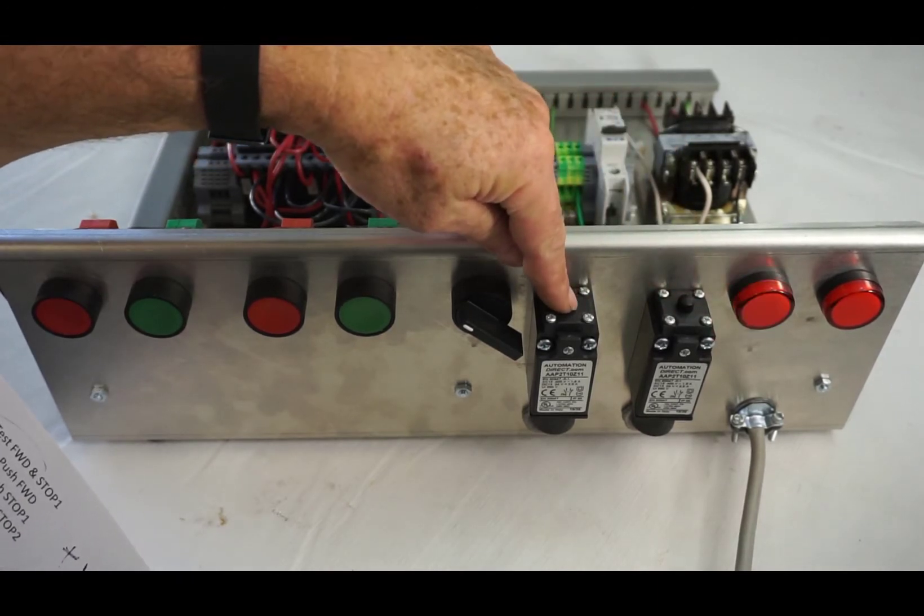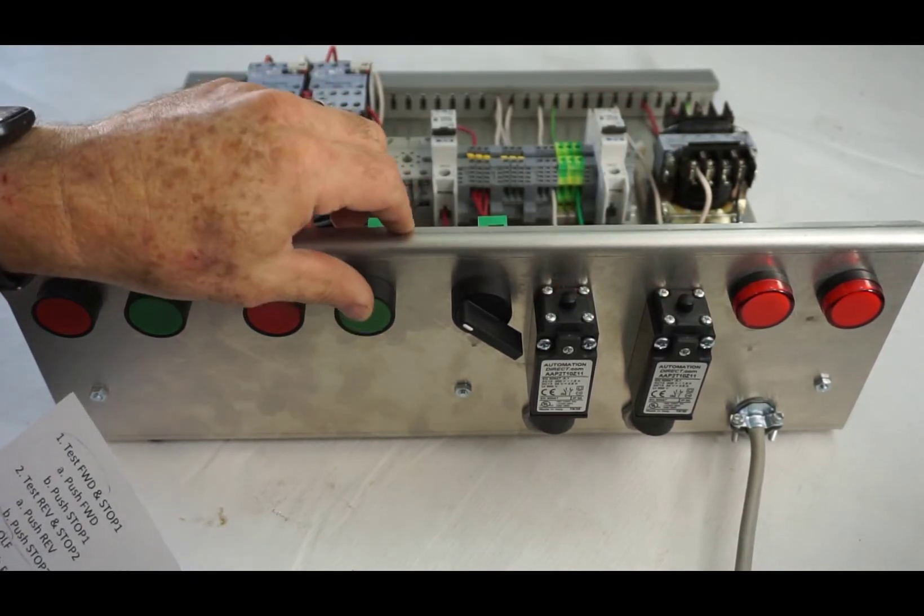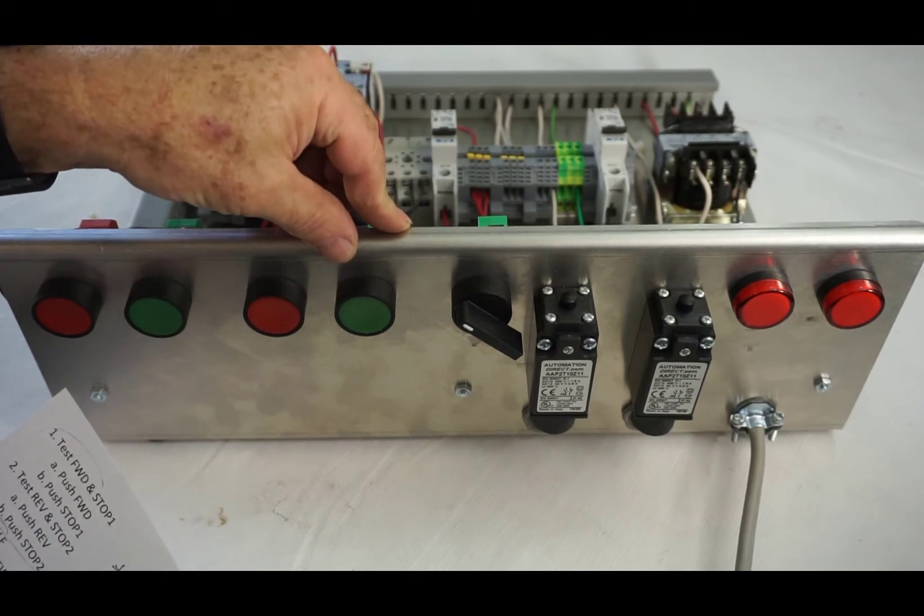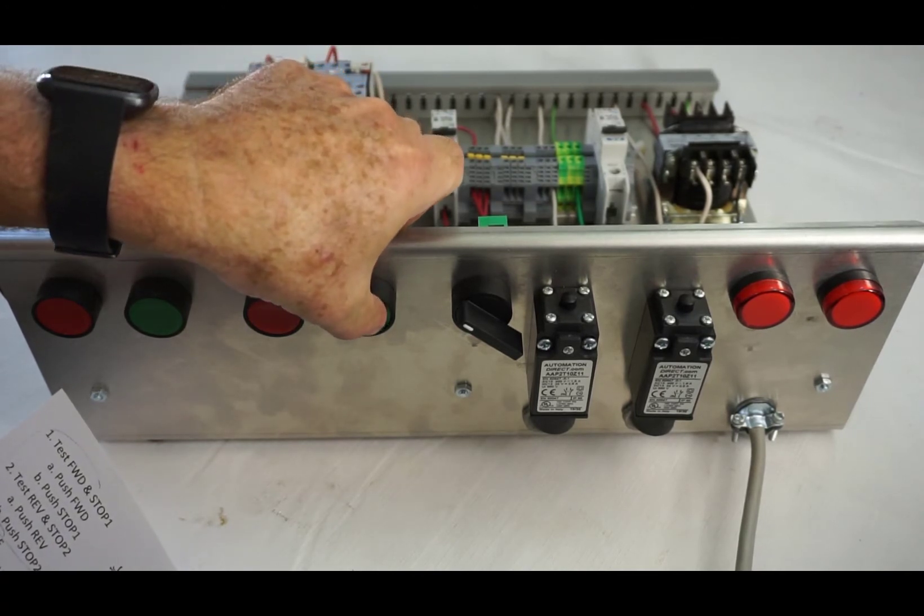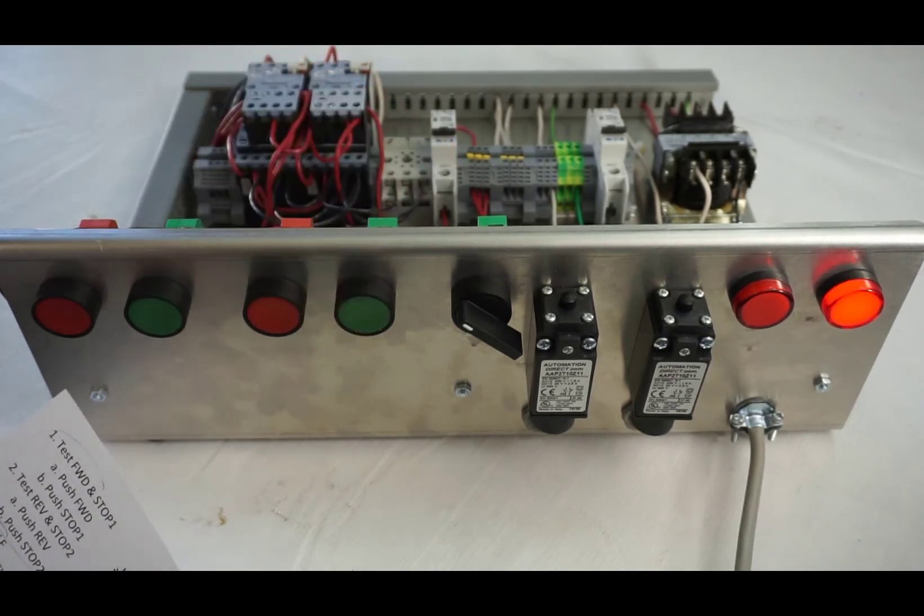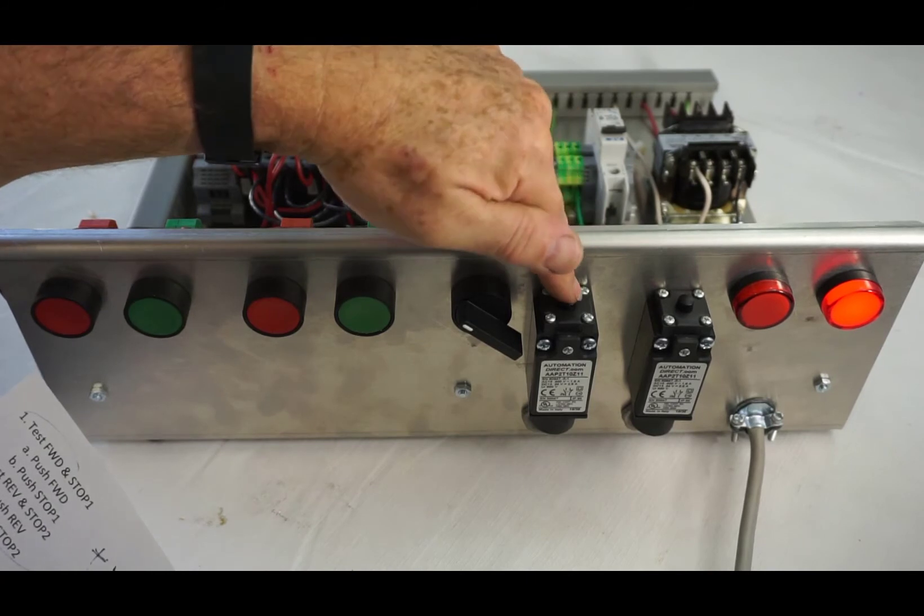Now we're going to do the same thing for the reverse side. Push the reverse start, push the forward limit. Nothing happens. The reverse limit, everything stops.